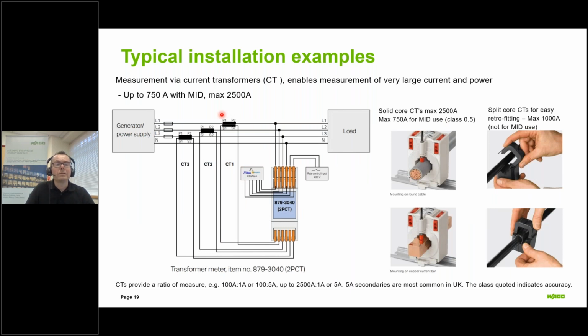The third version of the meter is the version used with current transformers. The current transformers simply measure a large current by means of a ratio. So for example, 100 to 1 amp or 100 to 5 amps, right up to 2,500 amps to 1 or 5 amps. And the idea is that by using the current transformer, either what's called a fixed core or a split core that's easy to retrofit, you can handle these very high loads, but only by measuring 1 or 5 amps, which obviously means the instrument, the meter itself, can be much more compact and in fact quite easy to install on existing systems.